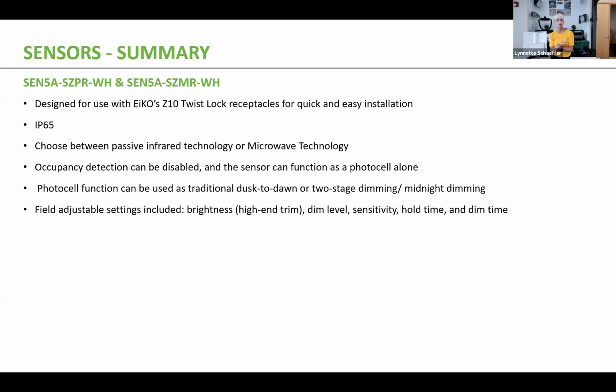You can also use field adjustable settings such as brightness, also known as your high-end trim. You can set your dim level, sensitivity, hold time, and dim time. All of these standalone control settings can be adjusted using the commissioning tool.